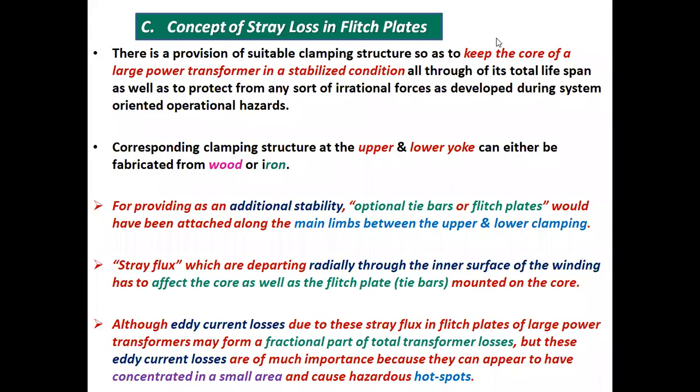Let's start with the concept of stray loss in flitch plates. There is a provision of suitable clamping structure so as to keep the core of a large power transformer in a stabilized condition throughout its total lifespan as well as to protect from any sort of irrational forces developed during system oriented operational hazards. Corresponding clamping structures at the upper and lower yoke can either be fabricated from wood or iron. For providing additional stability, optional tie bars or flitch plates would have been attached along the main limbs between the upper and lower clamping.